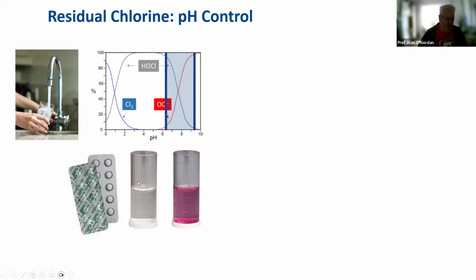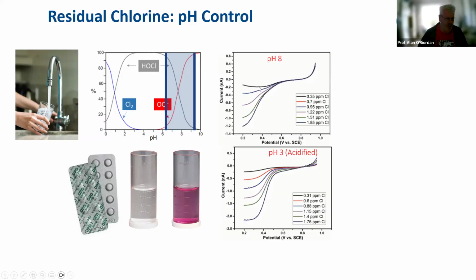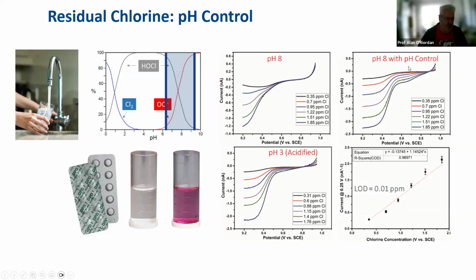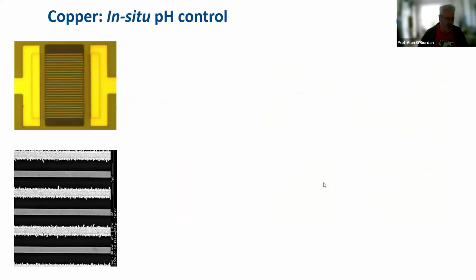So to do that, you have to add colorimetric and buffered chemicals to the solution. Here's an example. If you just do it at pH 8 electrochemically, you get this type of sample. If you acidify it, you get a much more sensitive measurement, which is what you want to do. If you acidify this, you're driving everything down into this regime, and you're measuring the gray here, the hypochlorous acid. And using pH control, you can see that the pH acidified with acids gives us the exact same data. So we're able to measure chlorine now without the need for any selective membranes or any added materials to the devices.